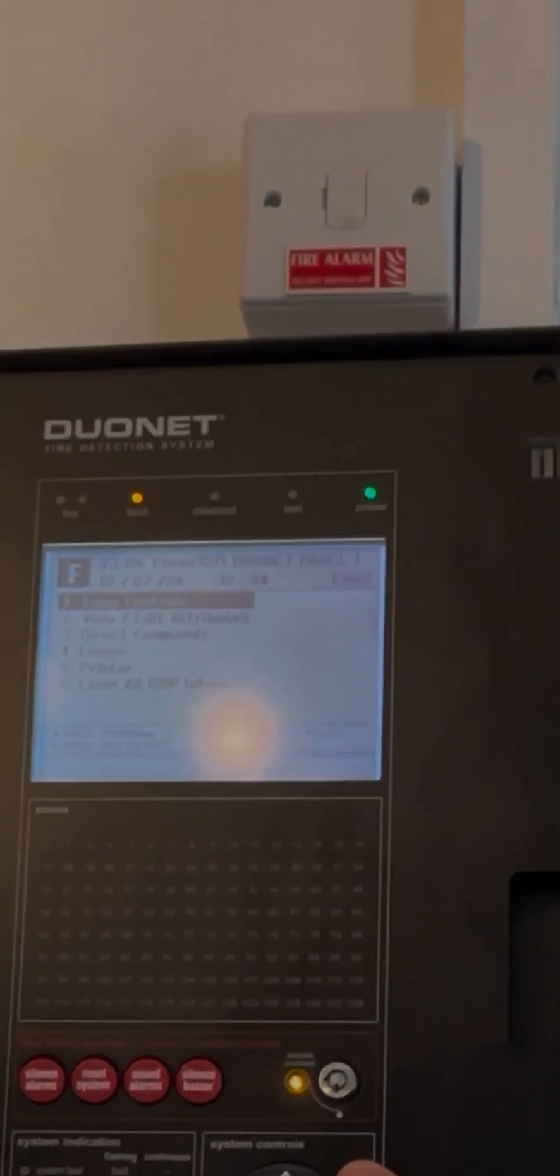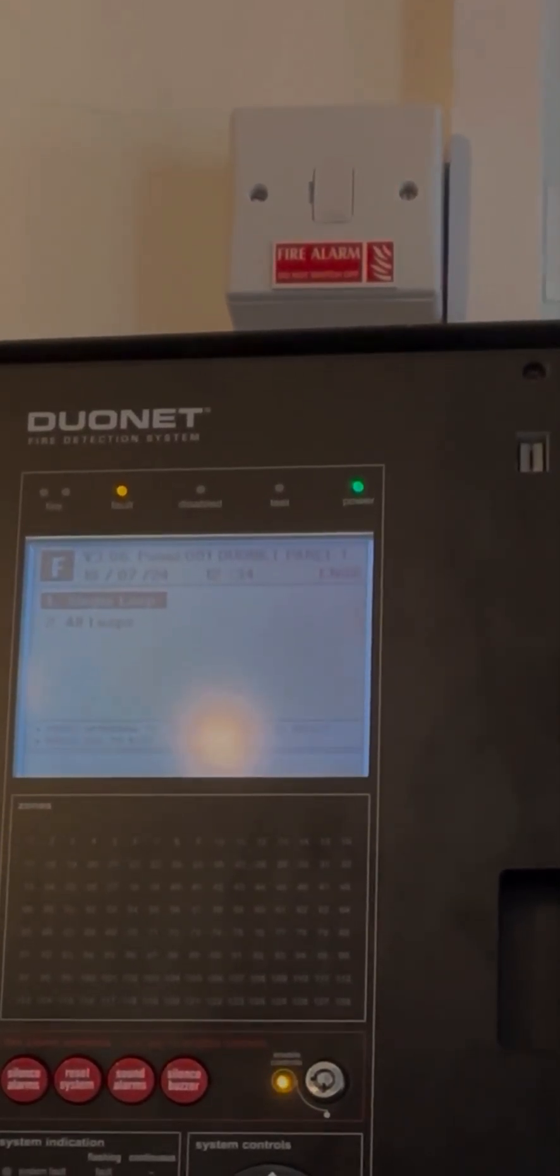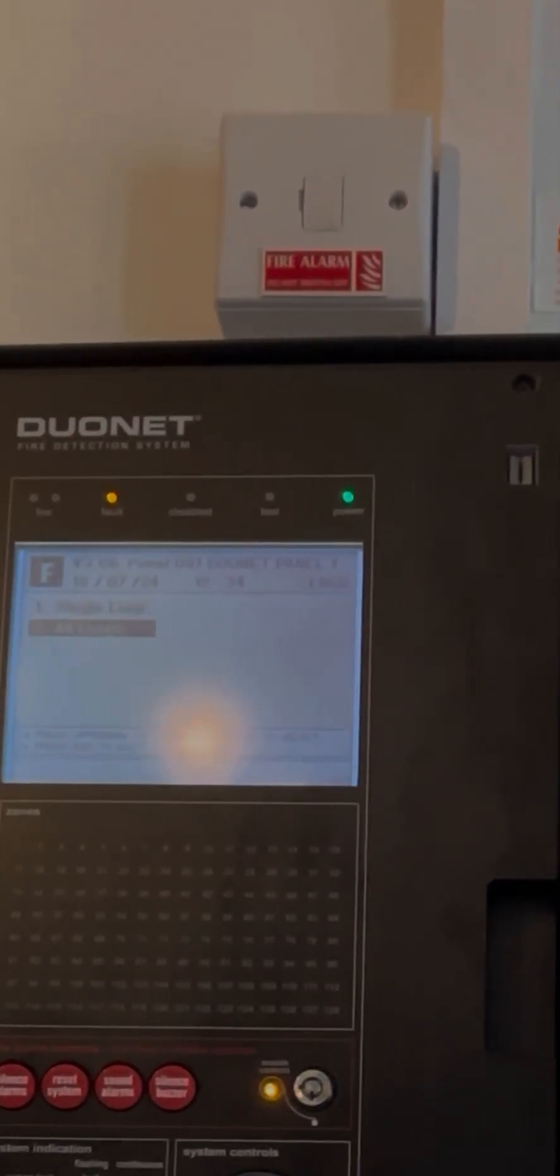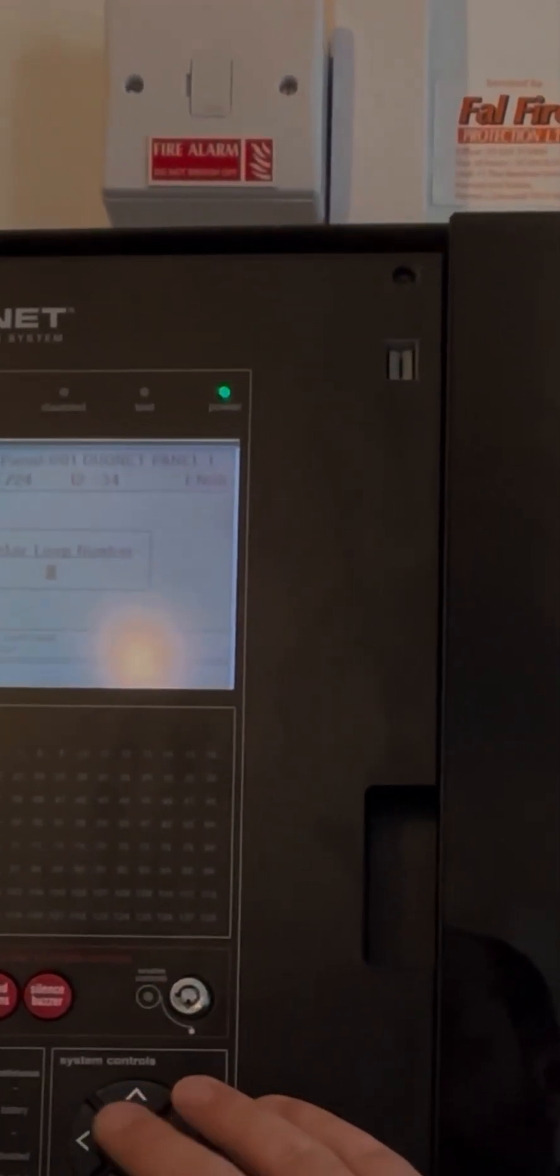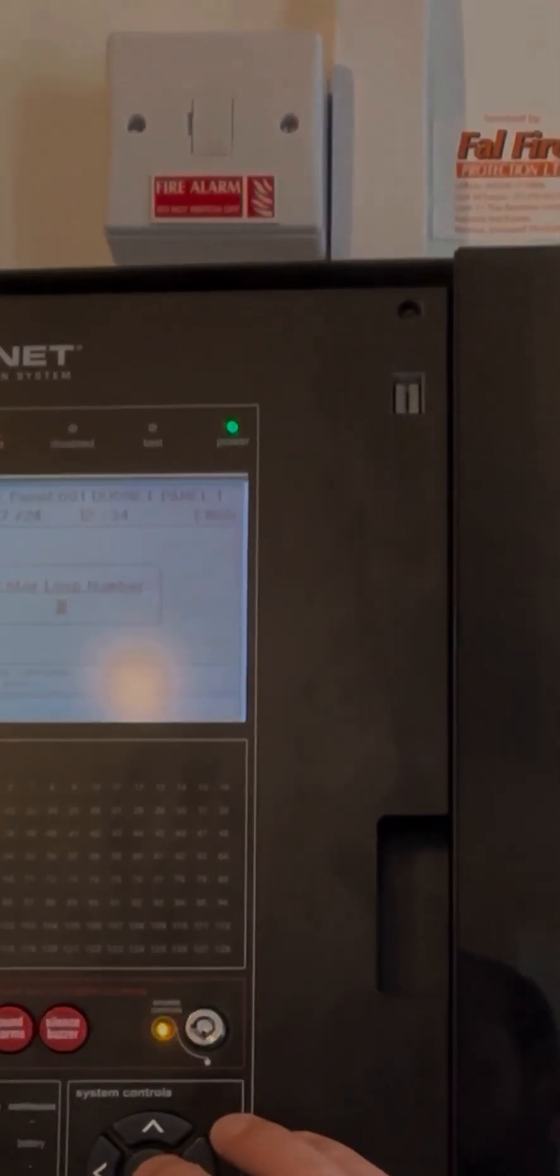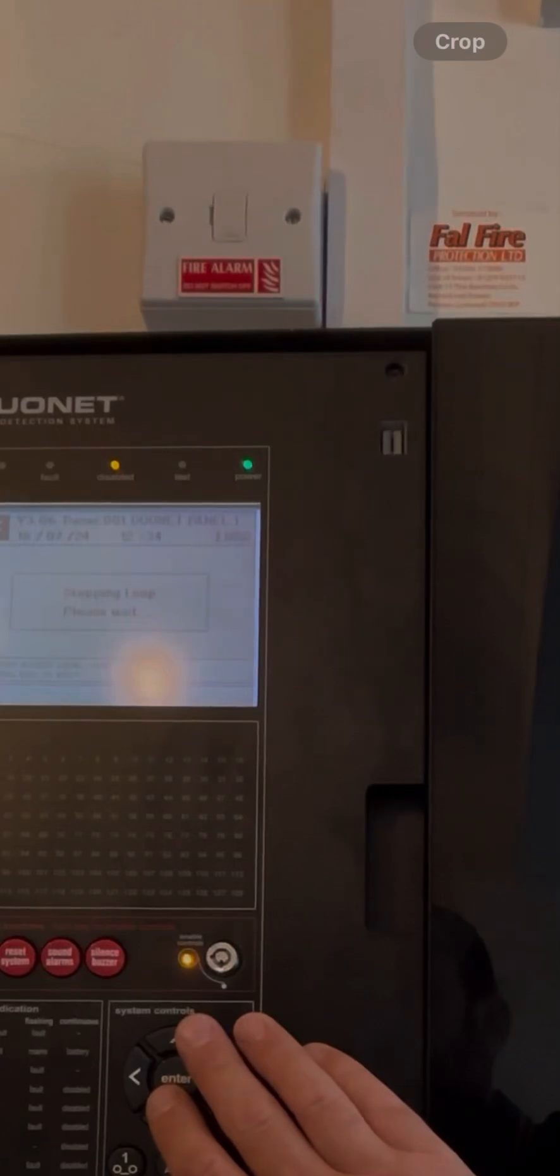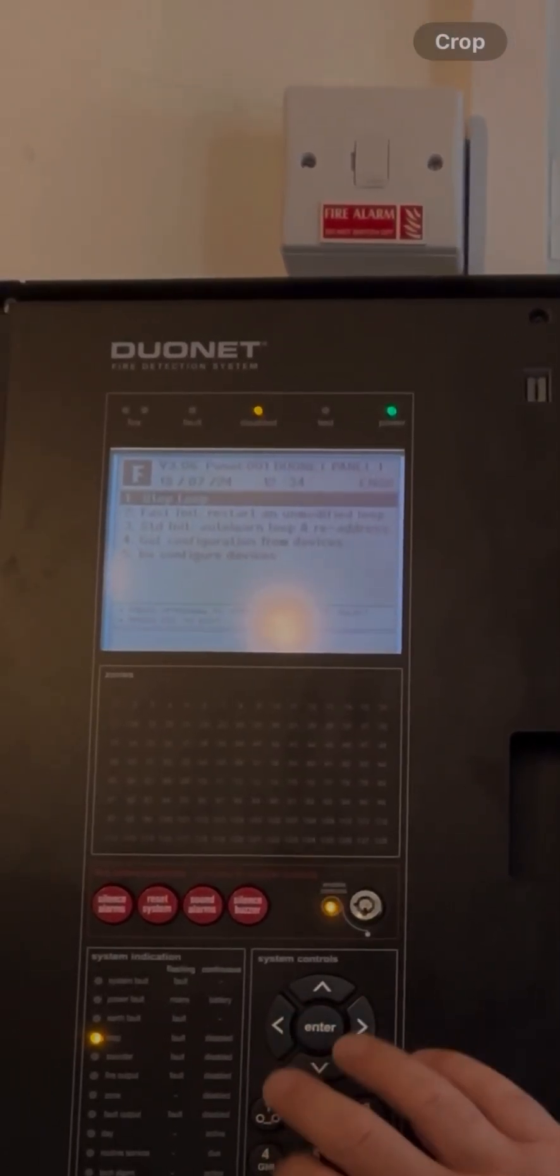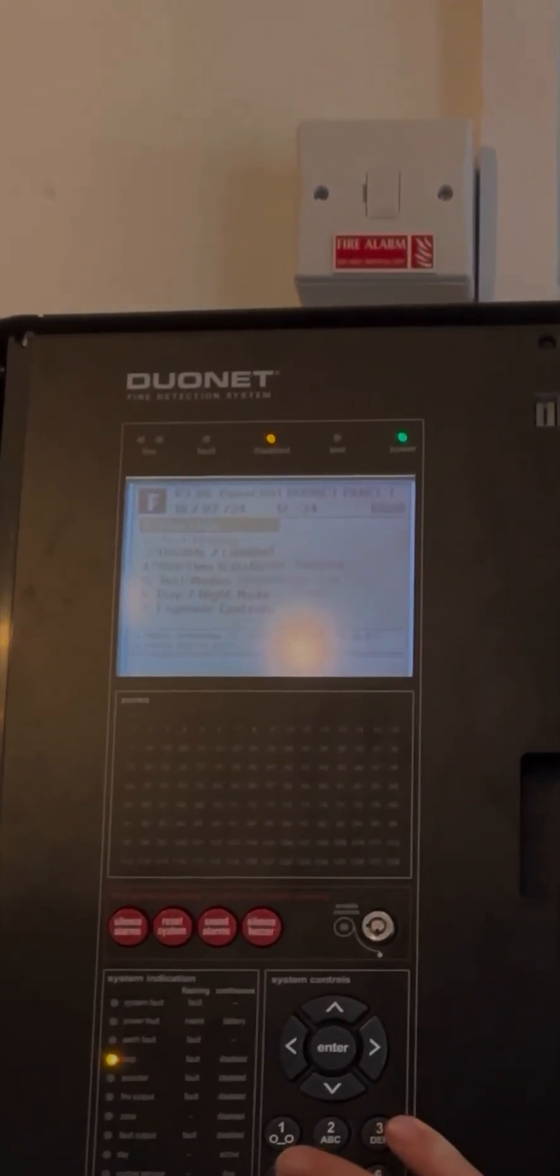This time, go into Loop Control and stop the loop. You can either use single loop or all loops depending on what you want to do. I'm going to go single loop on this occasion, but I've only got one loop anyway, so it really doesn't matter. Type in the loop you want to stop and hit the enter button. You'll see 'Stopping loop, please wait.' The disabled lights will come on. If you escape all the way out, that's your loop stopped.